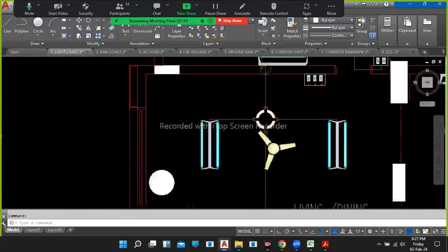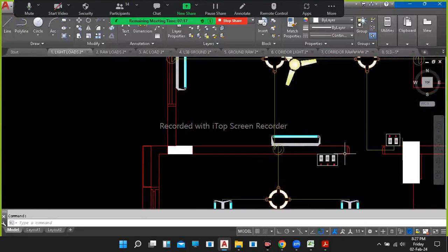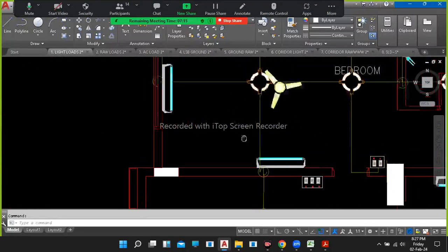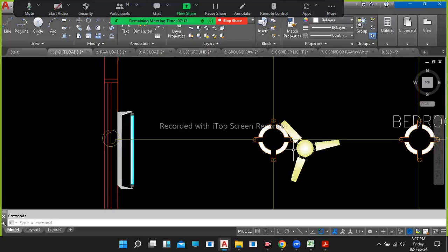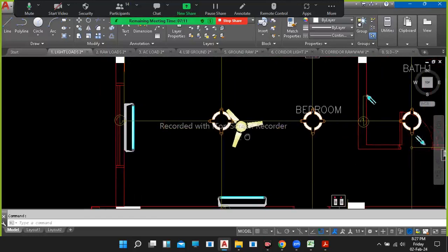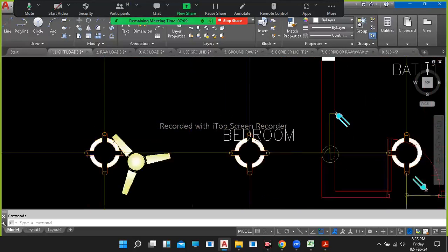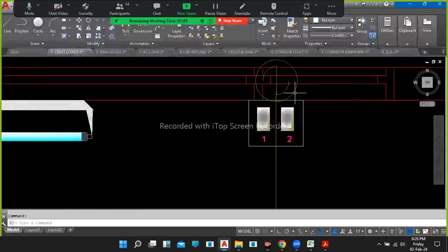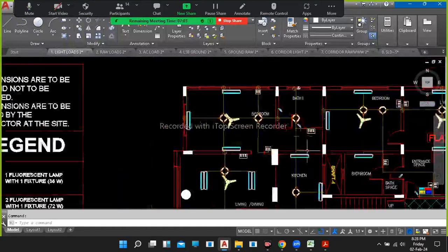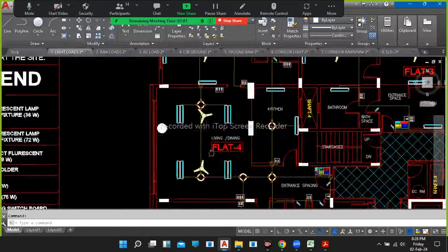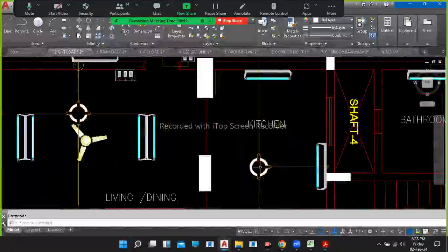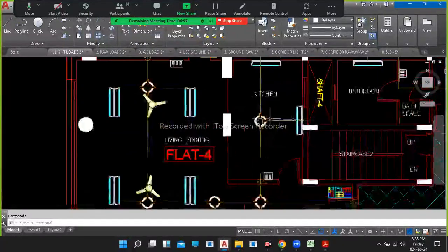And wherever you require tappings, from the same junction box I take a tapping and give it to multiple points. Near the switchboard we also need to give a symbol for drop, and near the equipment too. For fans we don't provide it since they're placed in the ceiling itself, but for all FL and CFL lights and switchboards we need to give the drop symbol. So make sure the main conduiting always runs from the center, and wherever tappings are required, provide a junction box and route tappings to all equipment.